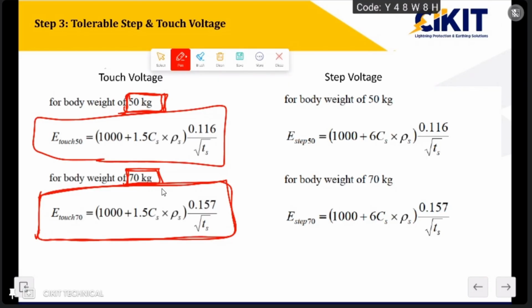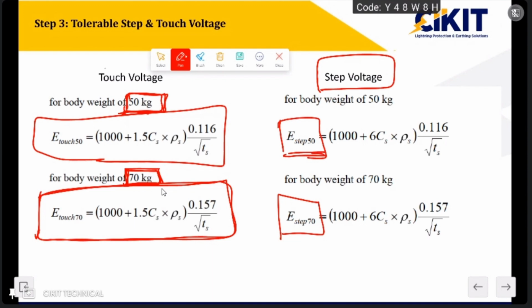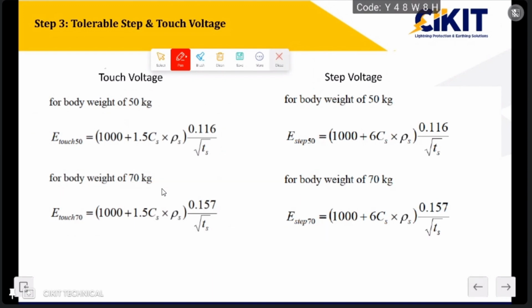So if I am performing the design by considering 50 kgs, then the persons who are 70 kgs will also be safe. But if I consider 70 kgs for designing, then for people lighter than 70 kgs, I cannot ensure safety. The same thing is applicable for step voltage also. For step voltage also, the value will be different for people with 50 kgs and people with 70 kgs. So from a safety point of view, it is recommended to go for the 50 kgs weight.